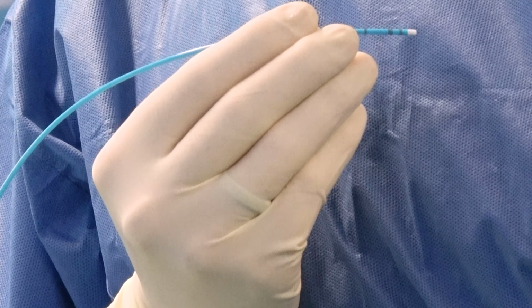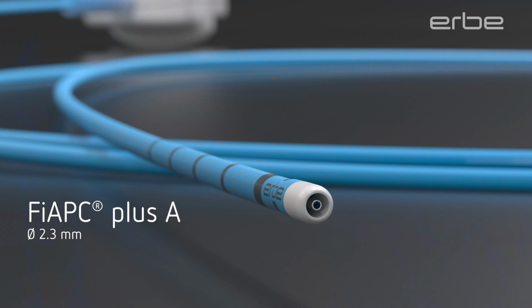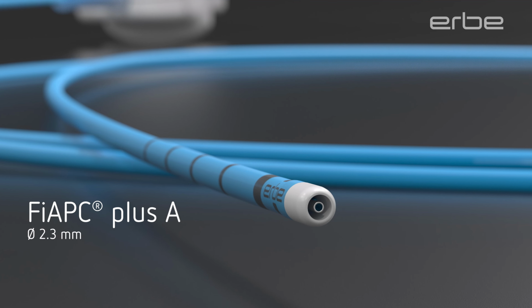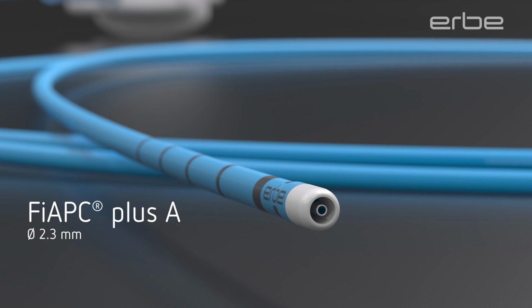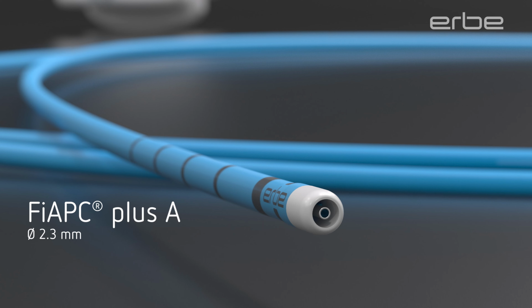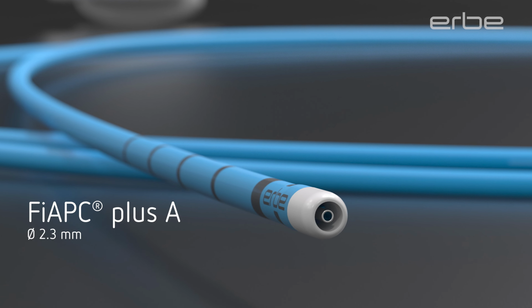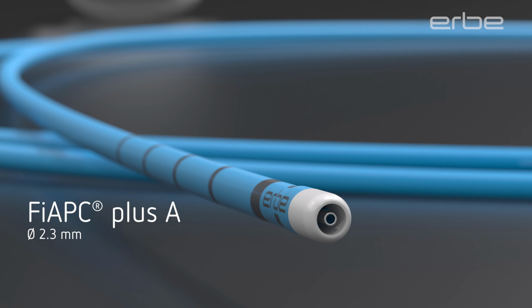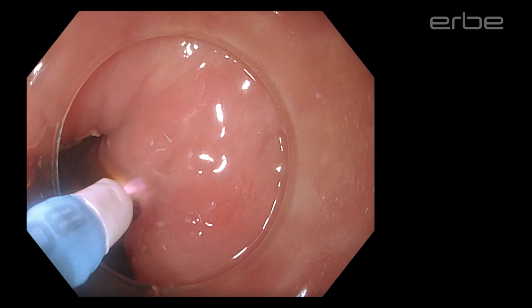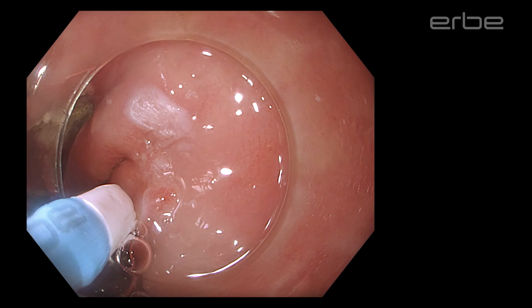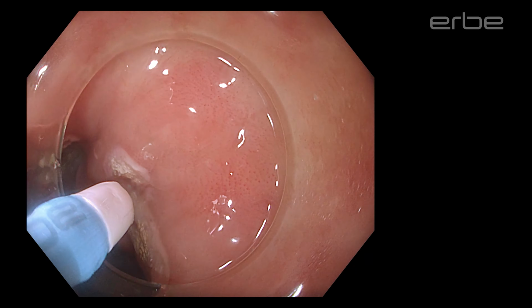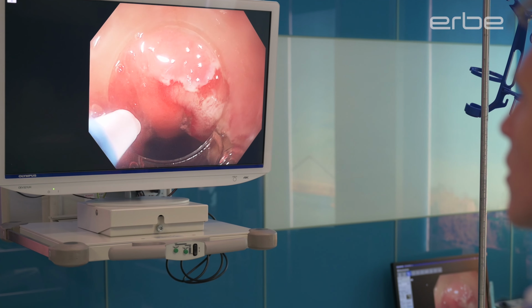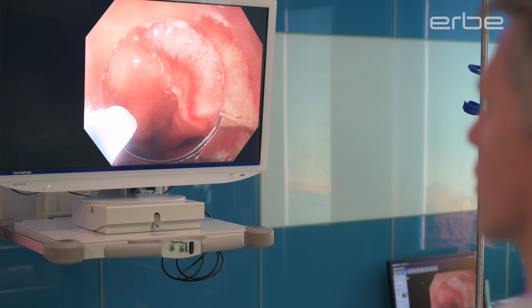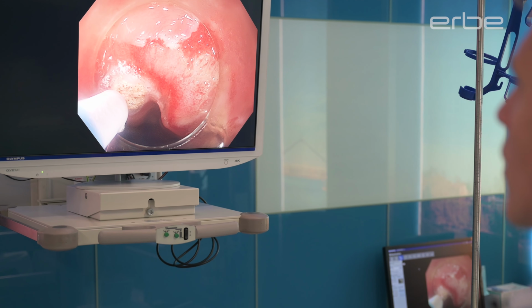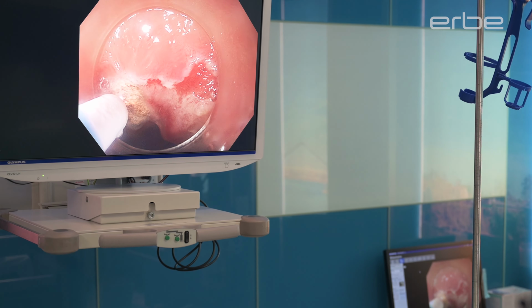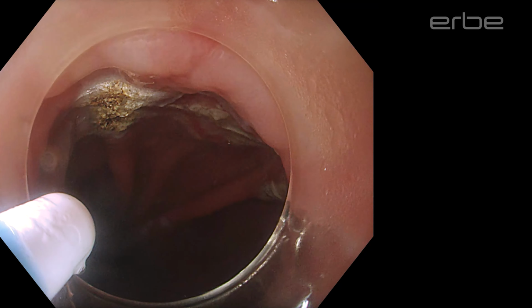I would like to show you the probe and the special design. So you can nicely see that we have here a novel tip design, so it's roundish, and we have a ceramic material of the tip, so that should prevent sticking of the tissue, of the coagulated tissue to the tip of the probe, and of course that should also create a more precise and focused plasma beam that will facilitate a more precise way to coagulate the tissue.